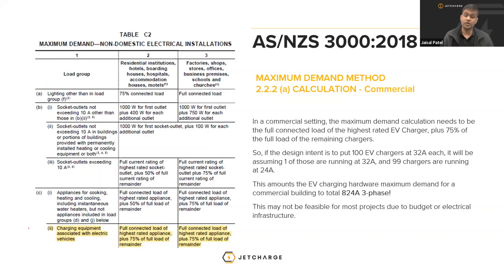Maximum demand for commercial applications is a bit different as well. In a commercial setting, the maximum demand calculation needs to be the full connected load of the highest EV charger plus 75% of the full load of the remaining chargers. So if the design is to put 100 EV chargers at 32 amps single phase each, it will be assumed that one of those chargers will be running at 32 amps and 99 of those chargers will be running at 24 amps, which is essentially 75% of the 32 amps full rated current.